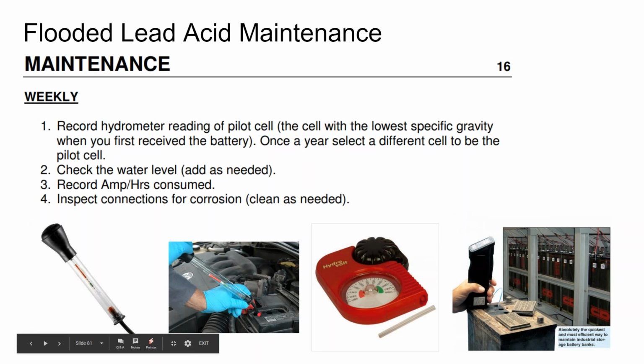With project planning, if you're going with industrial flooded lead acid, check the weights of the battery. That can become a logistical issue, because if they ship out on a standard pallet, that pallet's going to end up weighing over 3,000 pounds. A lot of your low-end machinery for moving stuff around may only have a weight limit, like a hoist that may only be able to pick up one battery at a time if it has a 2,000-pound rating.